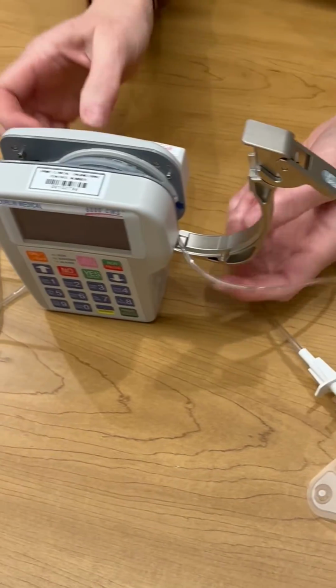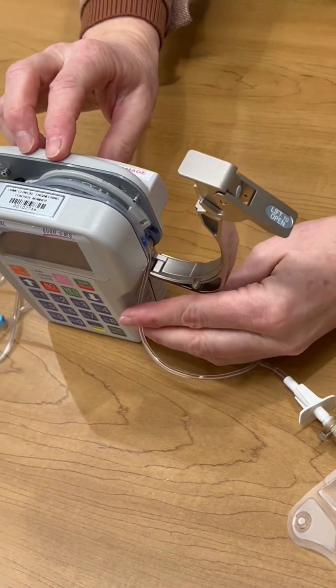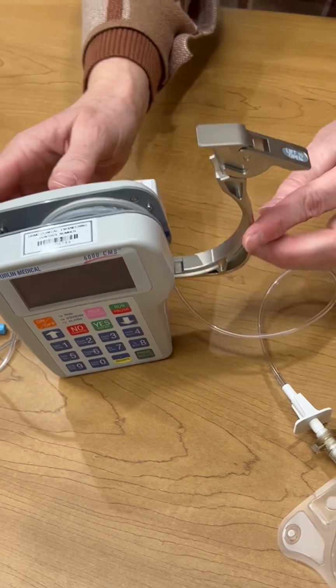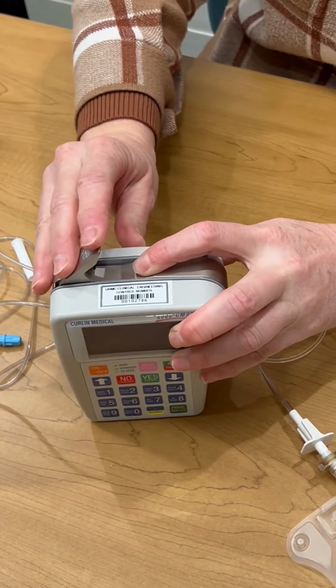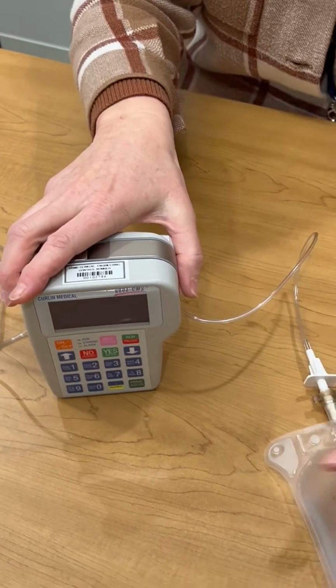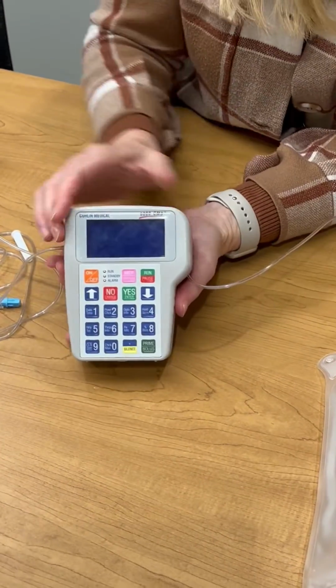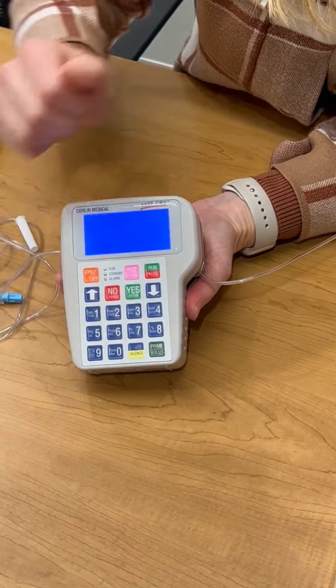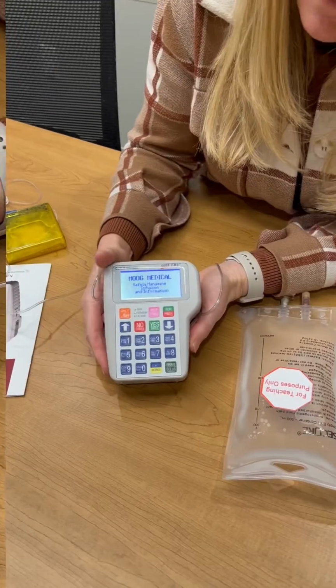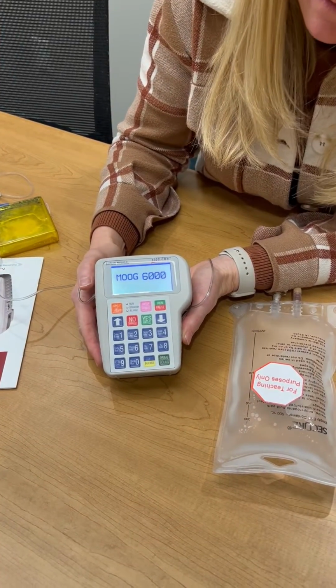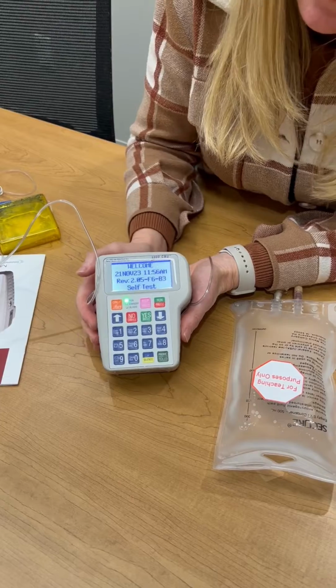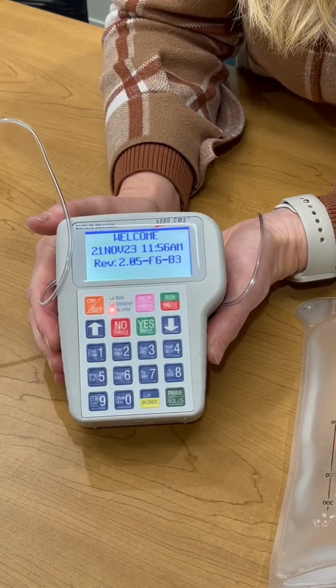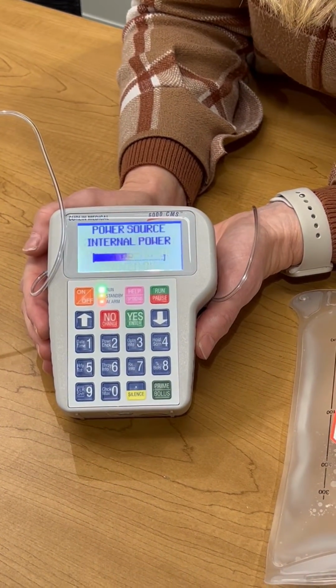There's an opening in the door for your tubing. So you're going to make sure the tubing is on that side. And then we're going to close the pump. All right, now we're ready to turn the pump on. That's the on-off button. And here you're going to find the name of the pump. It's going to go through the alarm checks, and then it's going to tell you your battery life.